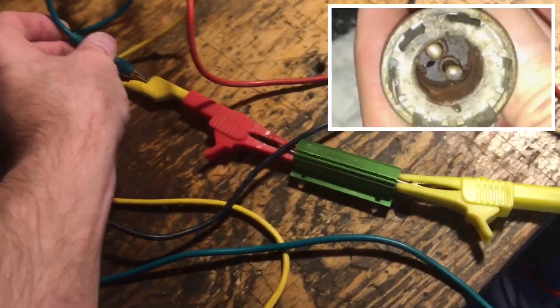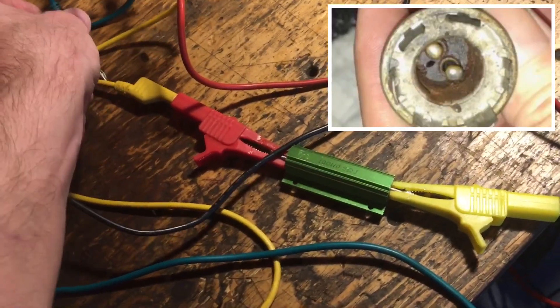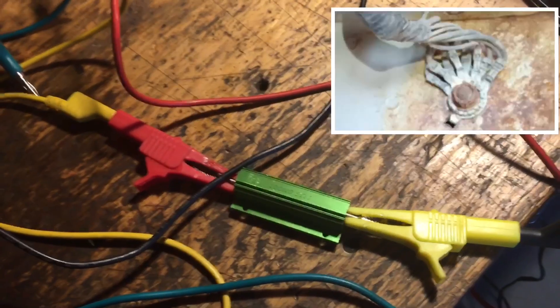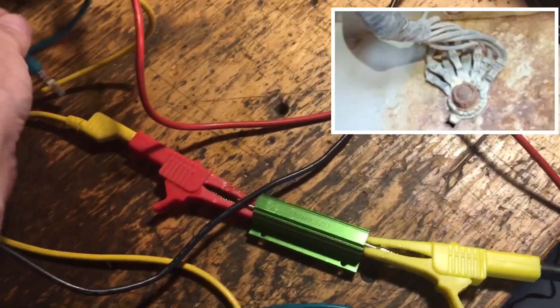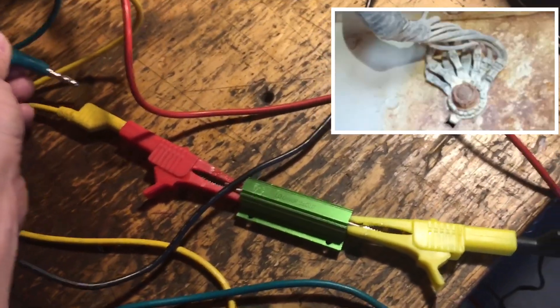Can you see the difference in intensity of the lamp there? That's with 0.5 of an ohm. So you see rust in a lamp holder or a ground or something like that and you think it's nothing. This is half an ohm resistance and look at the difference in intensity of the lamp.